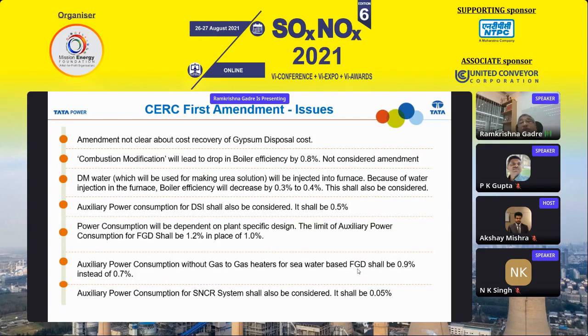If we are going for urea, a lot of DM water will be required for making the solution. In fact, when injecting this in case of SNCR, the boiler efficiency will drop because of a lot of water injection into the furnace. So SNCR has not been covered mostly in these regulations.